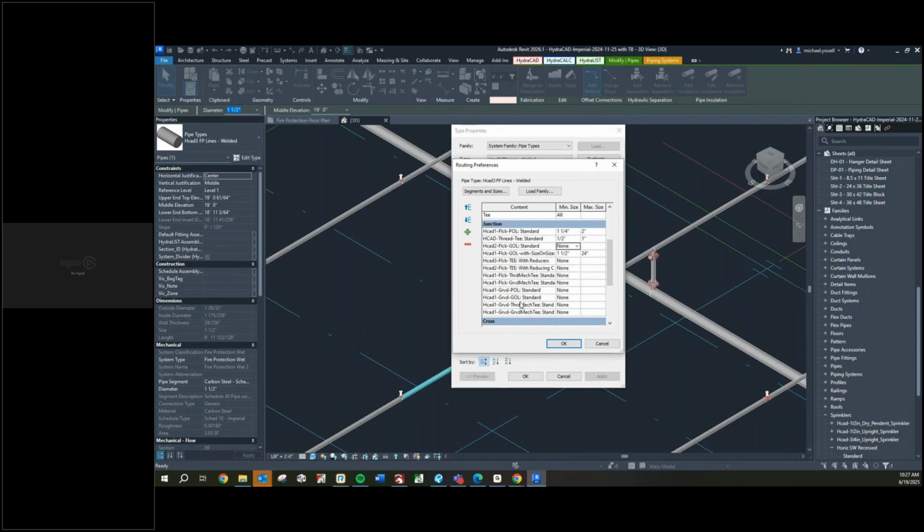Okay. I'm going to say the difference is the first one has been the standard for 30 years. The second one with size on size has been a standard for some folks for only 5 years. Because when they first started welding, they said, "Oh my God, you can't put an outlet that big on that pipe." And then somebody said, "Why not? I'll try," and they got away with it. Right. And since then, they said that's way cheaper than 3 couplings and a T. Got it.